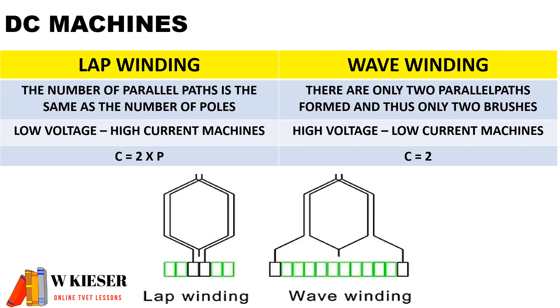Lap-winding is used for low voltage, high current machines, and wave-winding is used for high voltage, low current machines. For calculations, the number of parallel paths for wave-winding (c) is always equal to two, and for lap-winding, c is equal to two times the number of poles.